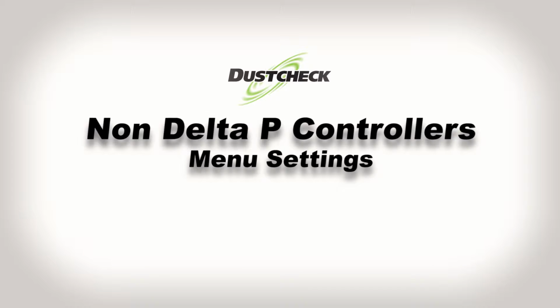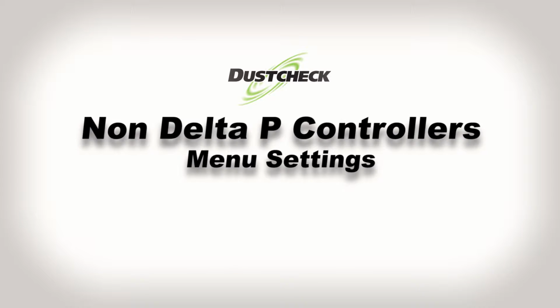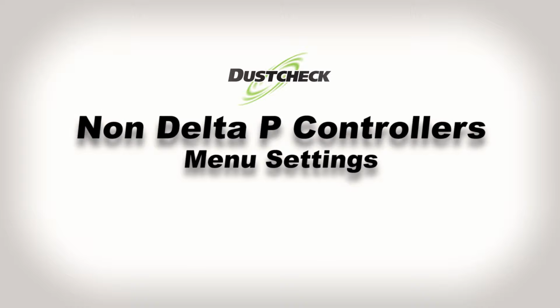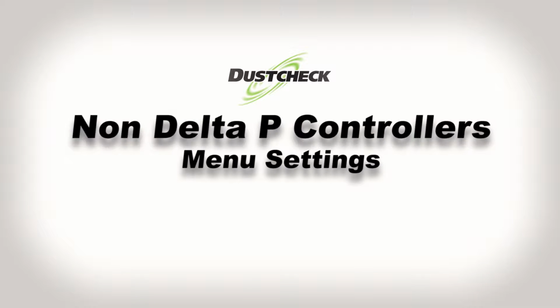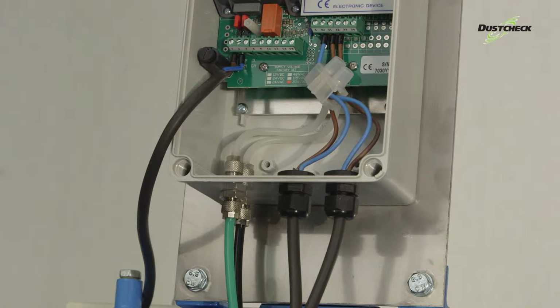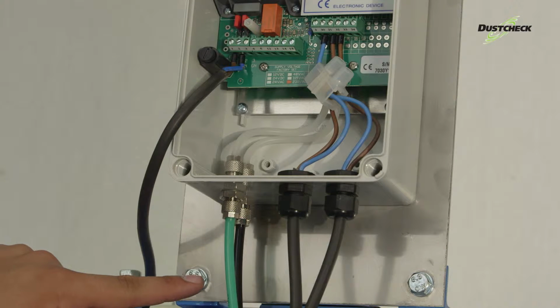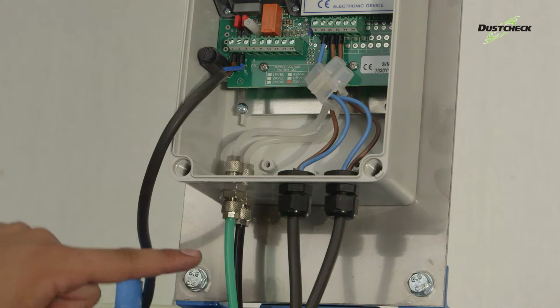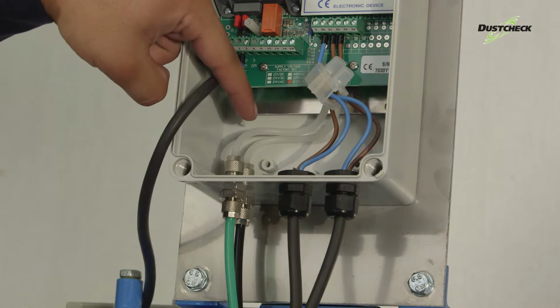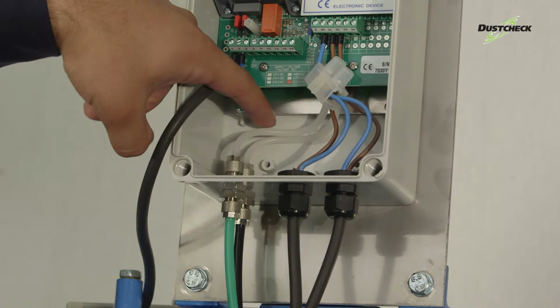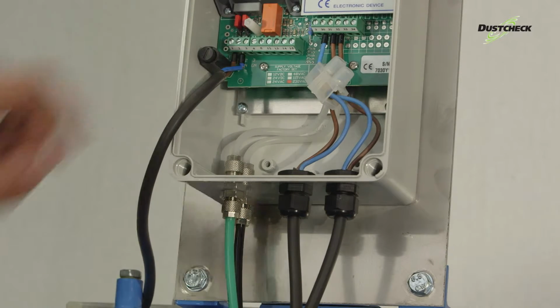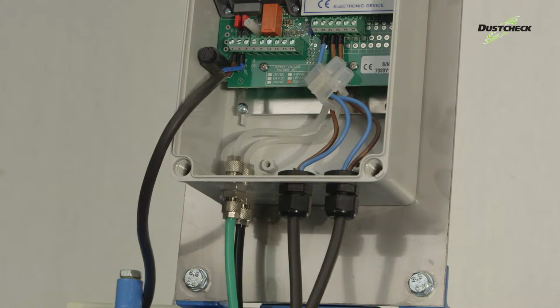This film shows how to set up the various parameters on a Dustcheck sequence controller without a Delta P control facility. To establish if you have a Delta P controller, look for two pneumatic connections on the side of the controller, connected internally with plastic pipe. If your controller does have these, then you have a Delta P controller, and this video is not applicable. Instead, please view our Delta P controller film.